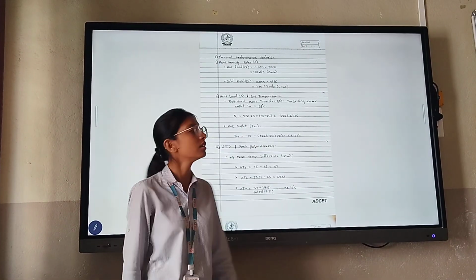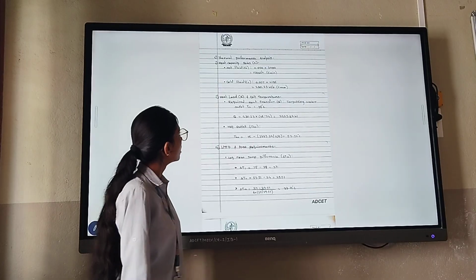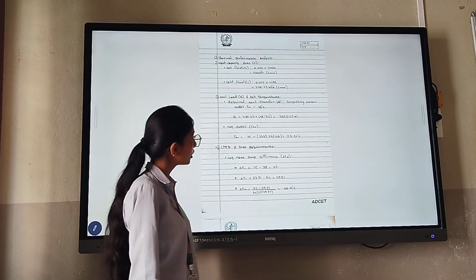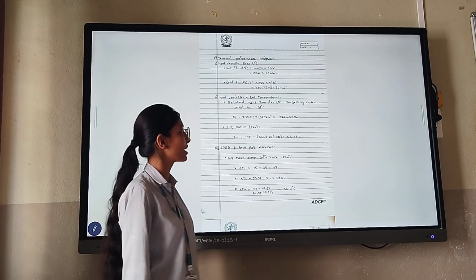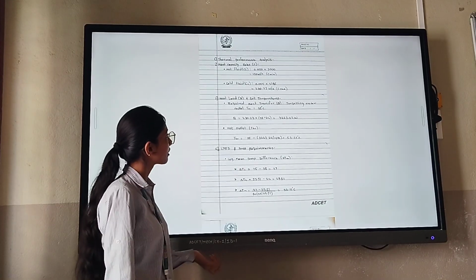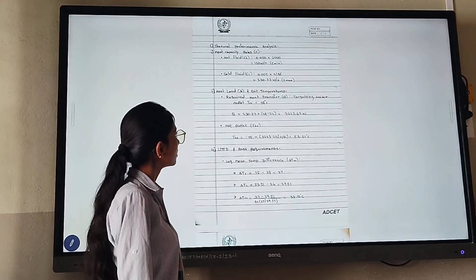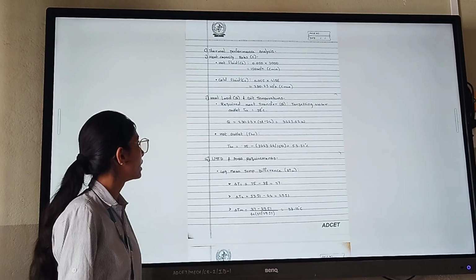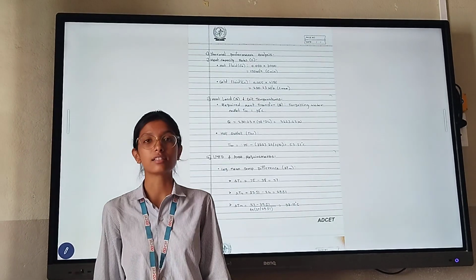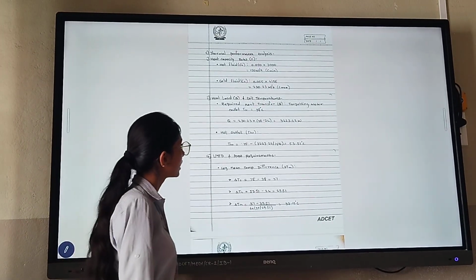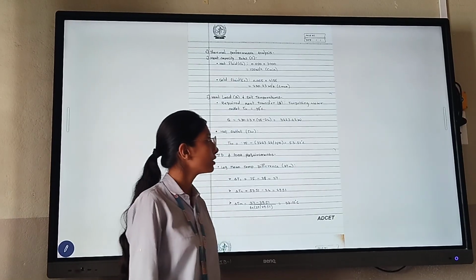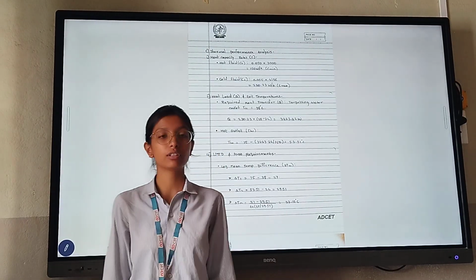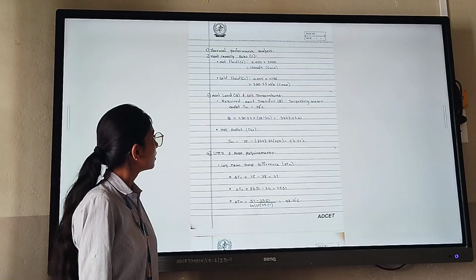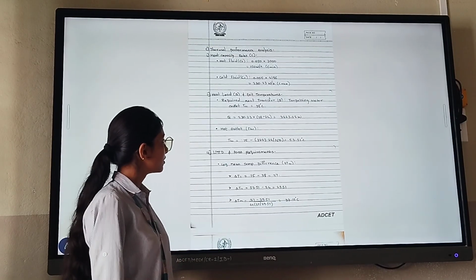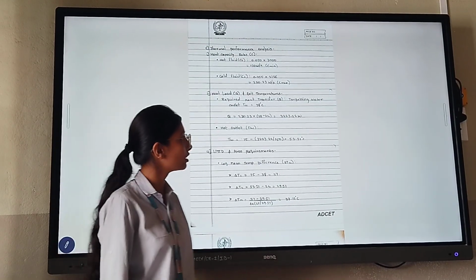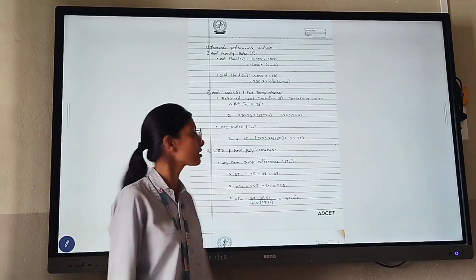330.23 watt per Kelvin. Then heat load and exiting temperature. Required heat transfer to target water outlet equals 38 degrees Celsius, and the calculated answer is 3223.2 watt. Hot fluid outlet calculated 53.51 degrees Celsius.